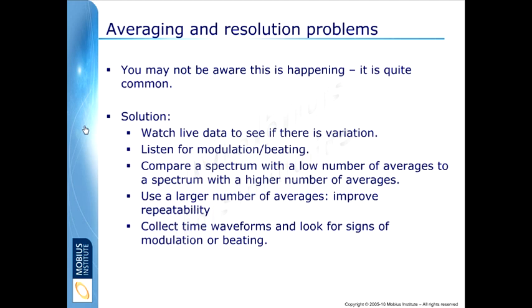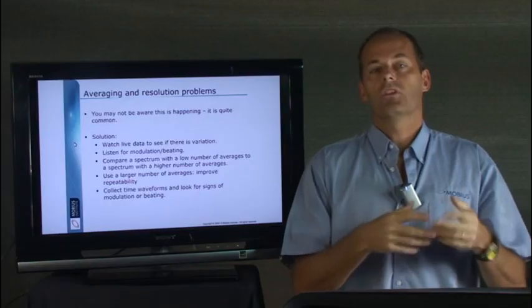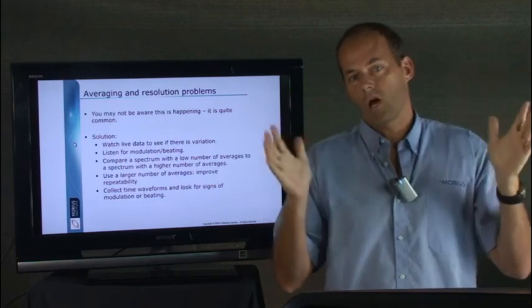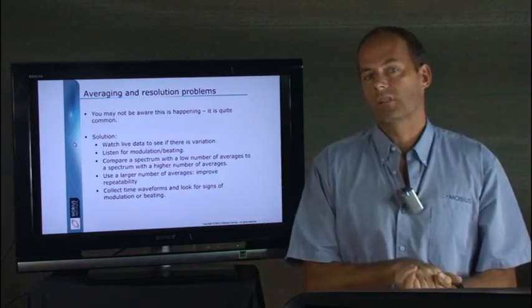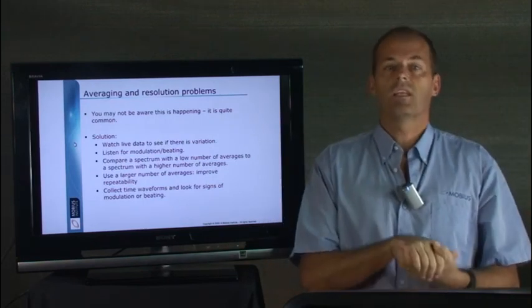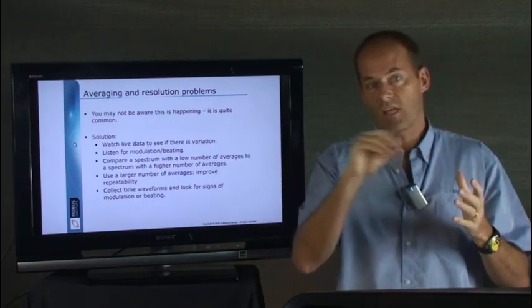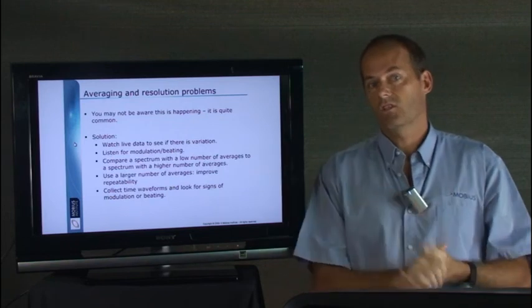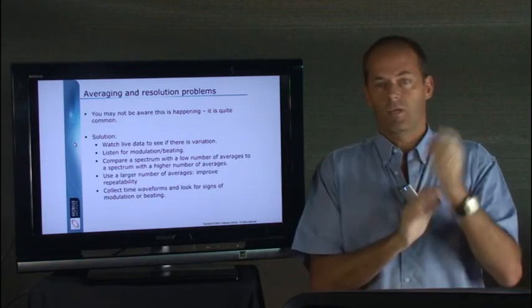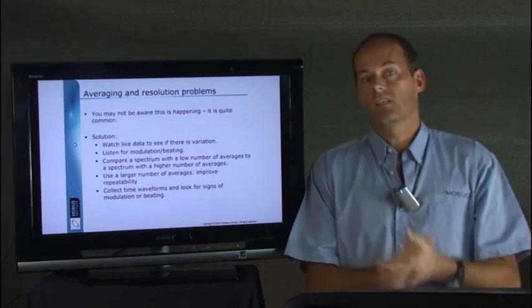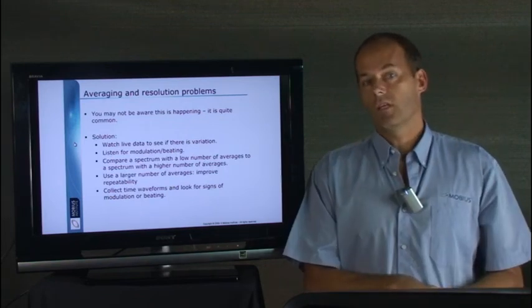And then if you've got a time waveform, you may see that there's modulation. The trouble is you normally need more time than you would normally collect. You might need 10 seconds of time to see that sort of modulation as compared with just the milliseconds you might normally capture.